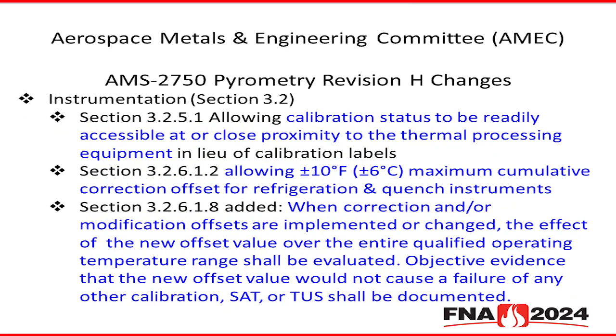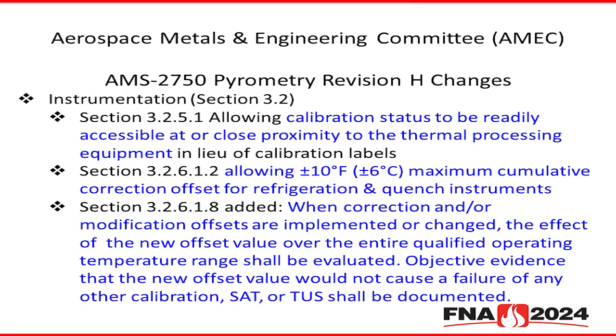Calibration status needs to be available. One of the things in this day and age, you see a lot of calibration systems that have moved to software that does your calibrations and keeps track of that stuff. And you always had to have a calibration label next to your instrumentation. Well, why do we have to have a label? Can we have something digital, maybe by the furnace operators, to know what the calibration status is? So we basically said you need a suitable means to know what your status is. Maybe you have a computerized system that's keeping track of the status of your calibrations, your TUSs and SATs. As long as that's available to the operators to know that they can run that equipment, maybe those labels are going to go away for you guys.